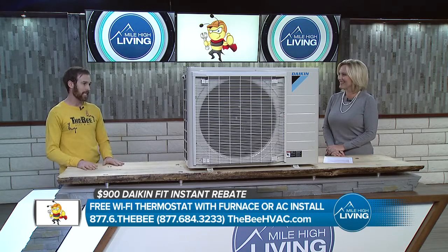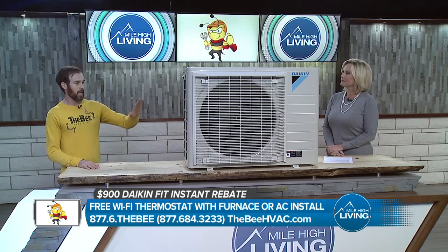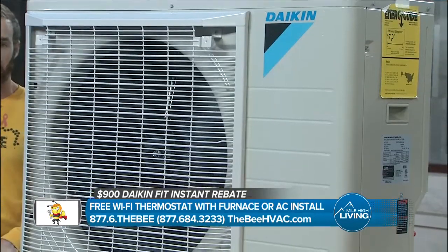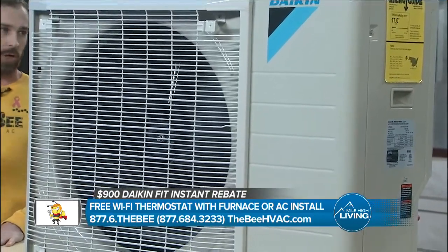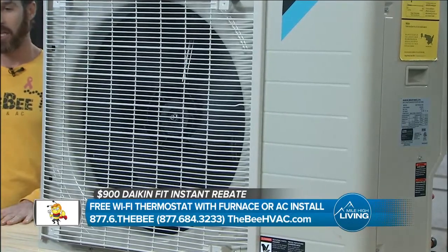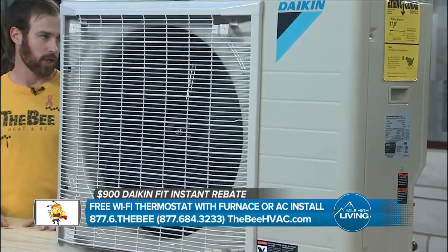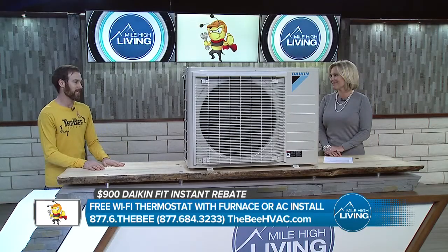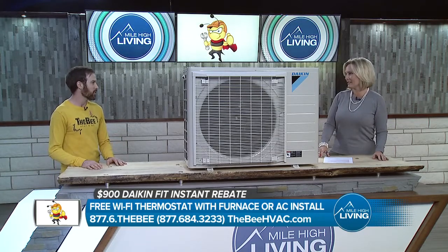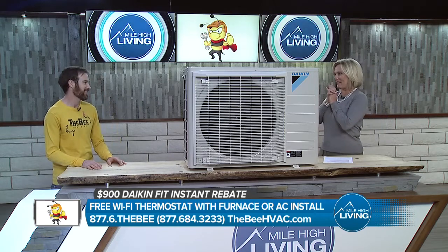The last thing — and we brought this for demonstration purposes — is to clean your condenser. On the side of the condenser you've got these fins that look kind of like radiator fins on a car. You want to make sure there's nothing clogging them. We get a lot of pollen in the spring out here, and in June things like weeping willow clog it up. Just hosing it off with a garden hose — don't use a pressure washer, that will damage it — but hosing it off is something really simple you can do.